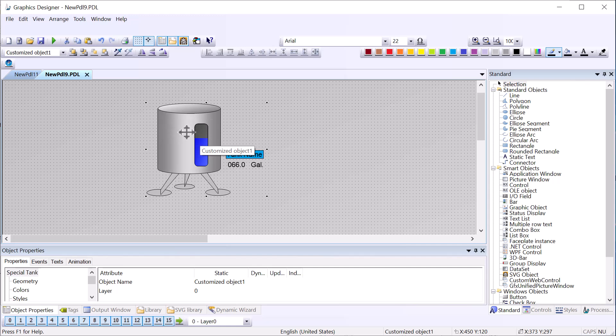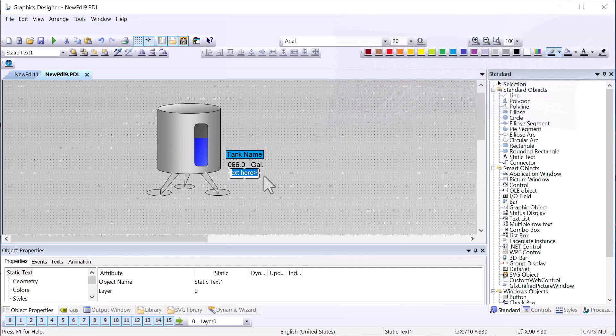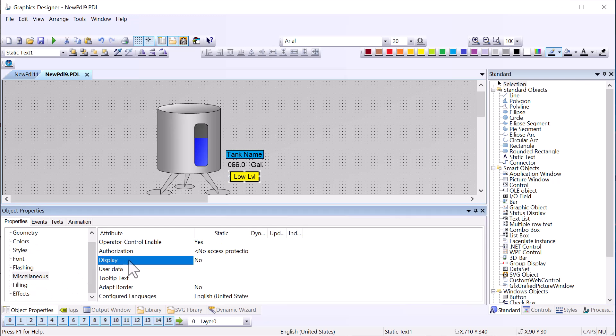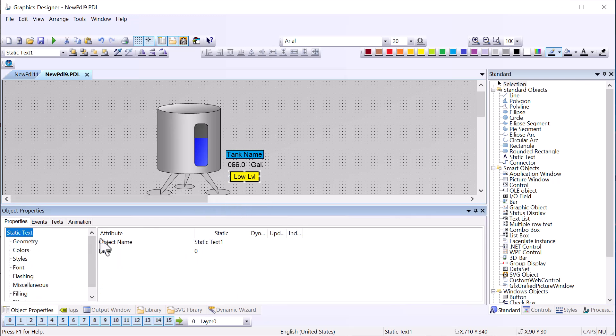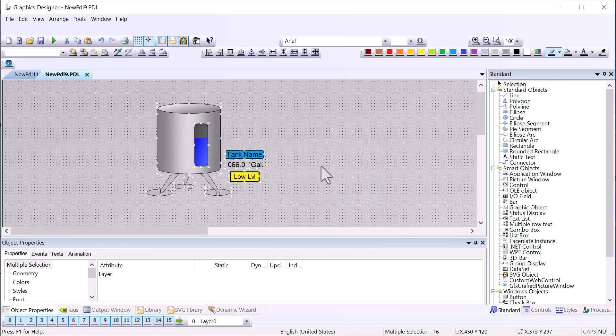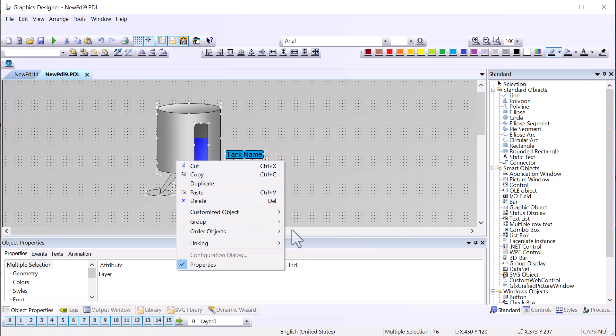Now let me show you one last thing. Let's say I need to add something to this tank or change the base property of something. I can right-click, go to Customize Object > Edit — it puts it into edit mode. Let's say I want a warning indicator down here — a low level indicator — the idea being it would show if the tank gets too low. I'll default it to yellow and set its display to No so by default it does not show. I'll give this a name: 'text_low_level'.